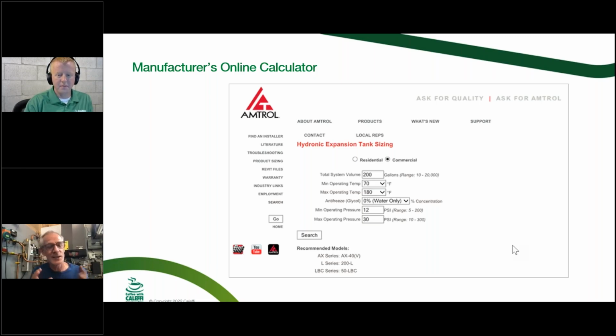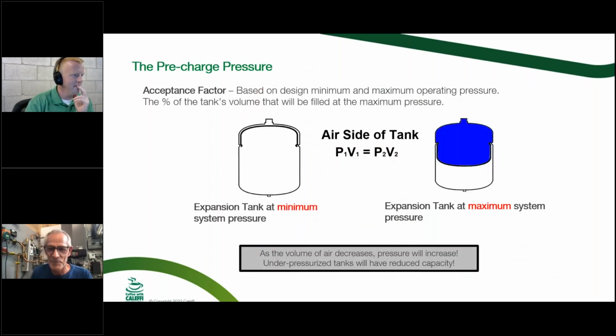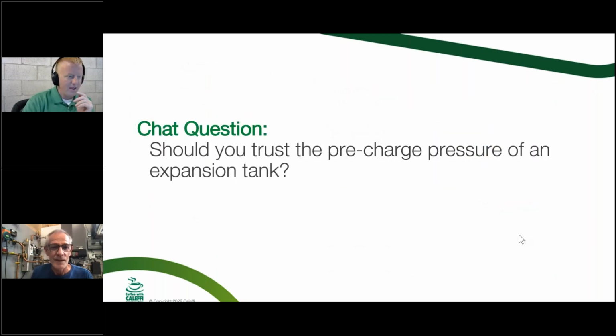And another interesting thing in there, it tells you even how much that tank is going to expand as you take it from 55 degrees to 180 degrees, and the volume of the tank increases because the steel wall of the tank actually expands, and it was like 8 gallons or something. This tank is going to expand, which again should go into the formula as your volume in your tank, I guess. So I'm going to back up a couple slides here.